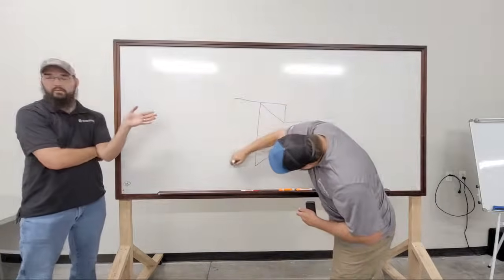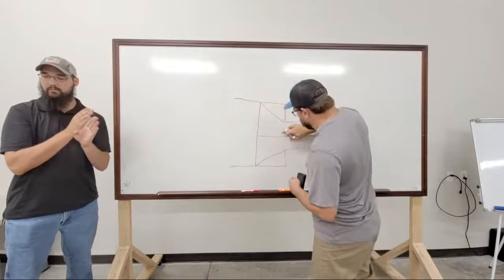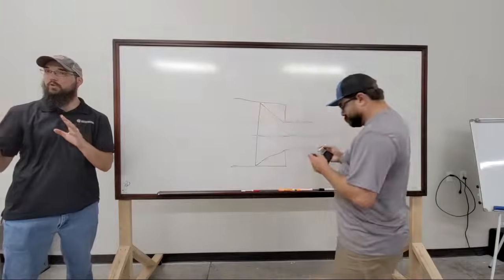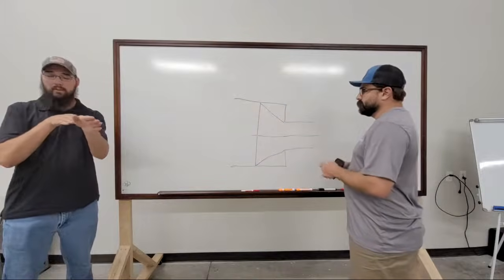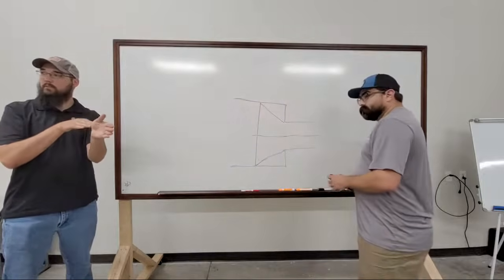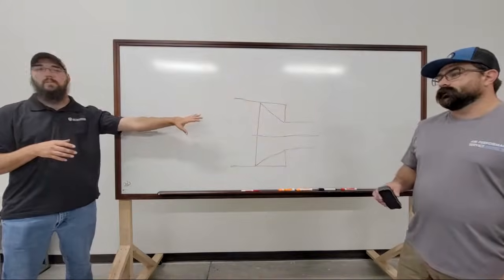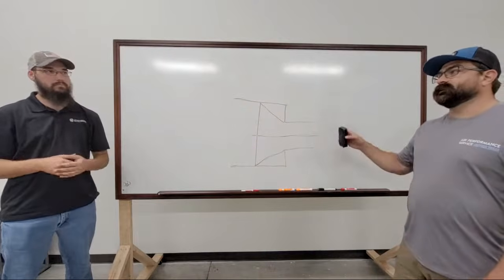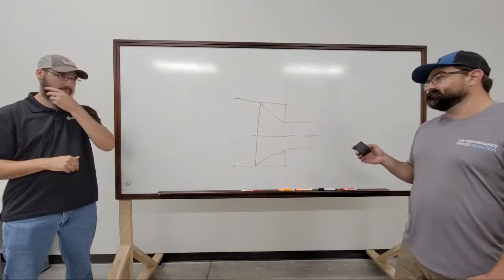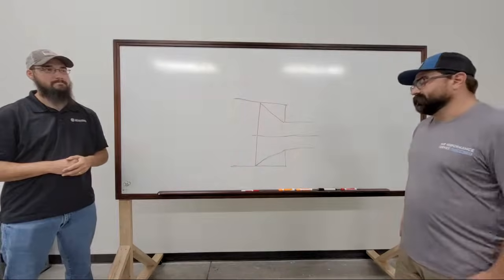This would be used in place of, instead of the flow control being done at the air handler, which a lot of your older systems most commonly did. They would have these dampers at the air handler and they would just be offset. It would all be done at the air handler. You wouldn't have a terminal unit downstream. This design was a way to try to fix Texas multi-zone setups and make it a little bit better control, but it's the same deal. It still sucks.